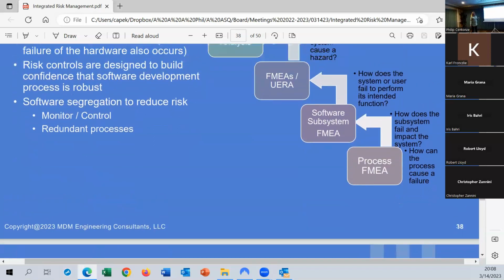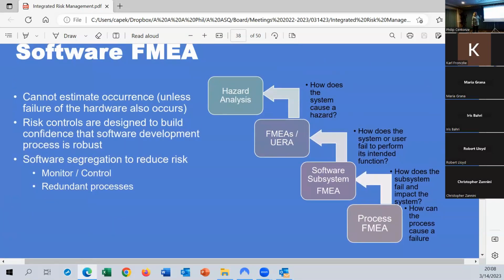Risk controls for a software FMEA are really intended to build confidence that the software development process is robust. Unless you have redundant processors or redundant algorithms, there's very little you can do other than say, well, I'm using a 62304 compliant process to develop software. But you could always have a monitor or a control that checks on each other. That's a way of controlling software.